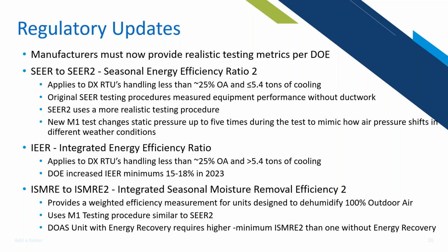One important note about the ISMRE rating is that DOAS units with energy recovery will now require a higher minimum ISMRE2 than those without energy recovery. Before, you could get away with accounting for the removal of humidification from the wheel, but now you will have two different ISMRE minimums for a DOAS unit. So if the DOAS unit has an energy recovery module, you will need a higher ISMRE rating.